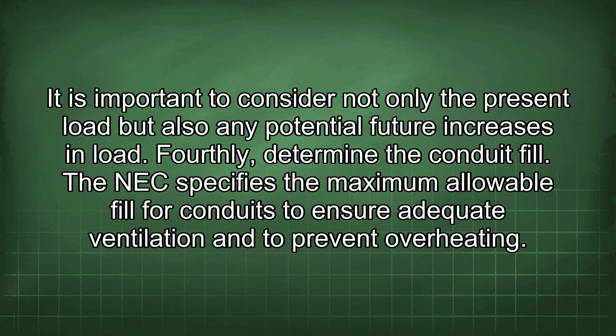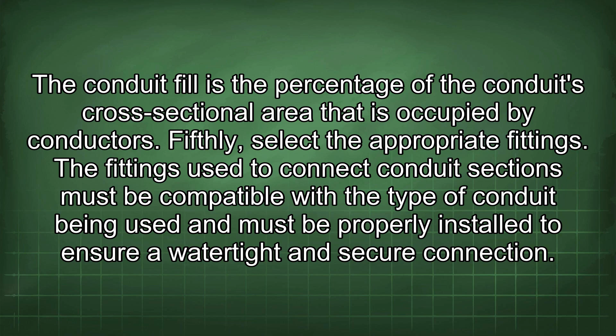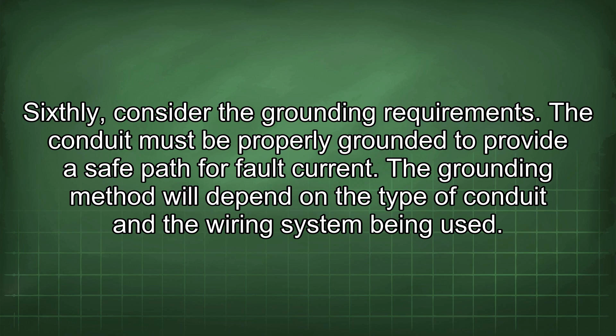Fifthly, select the appropriate fittings. The fittings used to connect conduit sections must be compatible with the type of conduit being used and must be properly installed to ensure a watertight and secure connection. Sixthly, consider the grounding requirements. The conduit must be properly grounded to provide a safe path for fault current. The grounding method will depend on the type of conduit and the wiring system being used.